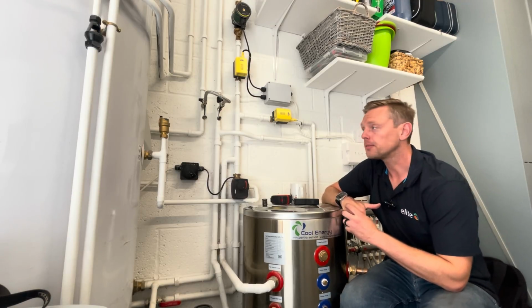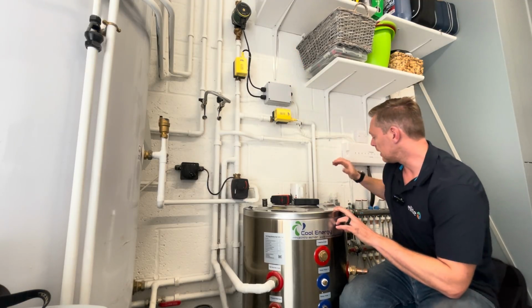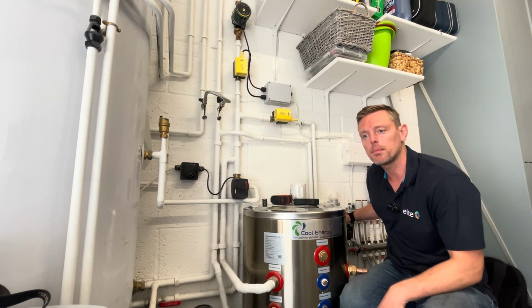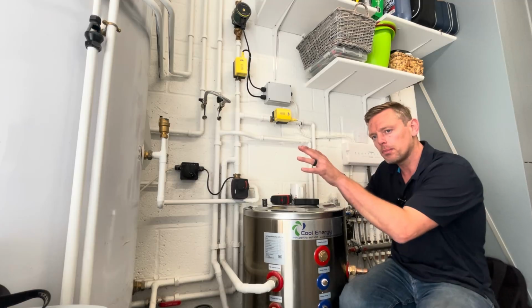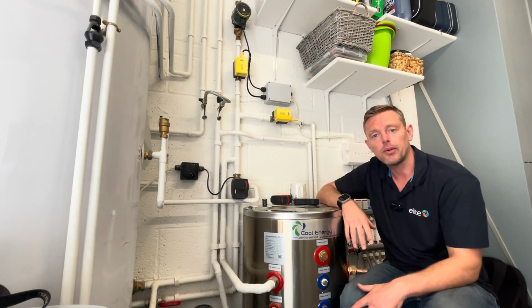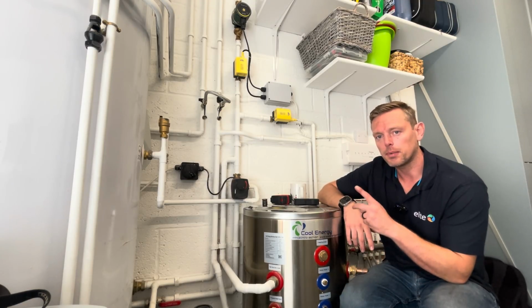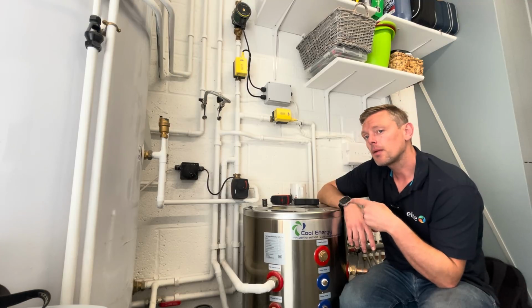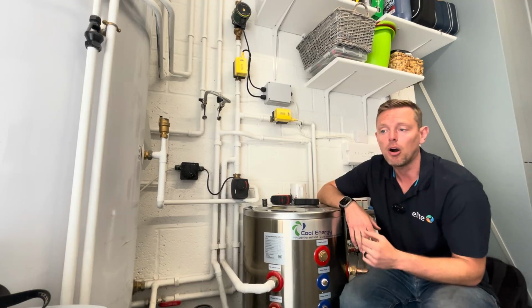Other things that we've noticed is that there is a pump on the heating circuit there and a pump on the underfloor. Now, we could probably get away with them putting the pump on the underfloor side of things because it's kind of hydraulically separated from the pump in the outdoor unit, but that one isn't up there. I'm very surprised that the Daikin unit hasn't come up with a fault code, a flow fault, because pump on pump it normally brings that up, but that's not going to help things. That's going to confuse the pump outside, maybe speed it up when it doesn't need to and modulate down when it's supposed to be gaining more.